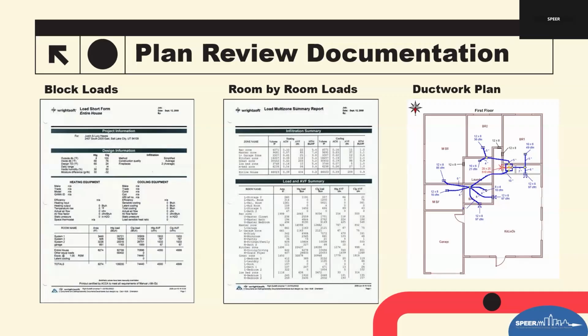So as a reviewer, you need to verify supply and return locations. Every major room has a supply, especially bedrooms. The returns must be appropriately located to avoid dead zones. This one just has a simplified return in the center. It looks like they're also showing on those plans 12 by 8 pass-through vents that are return pathways back to the system for return. So that's a good way for that to be done.